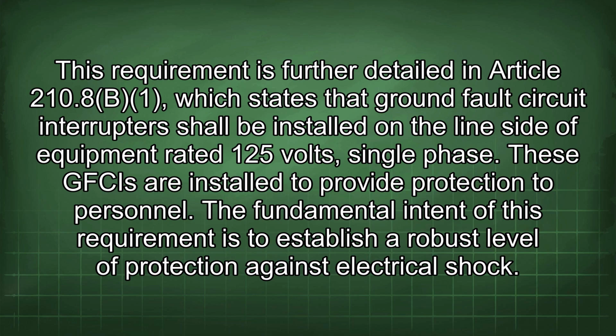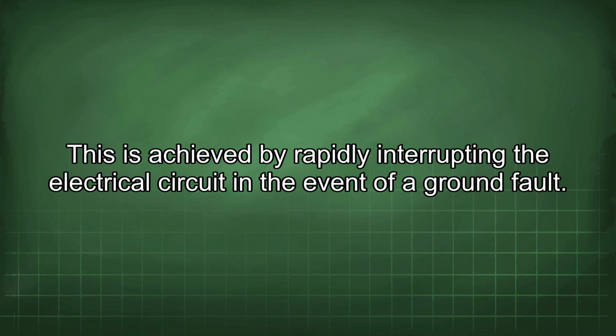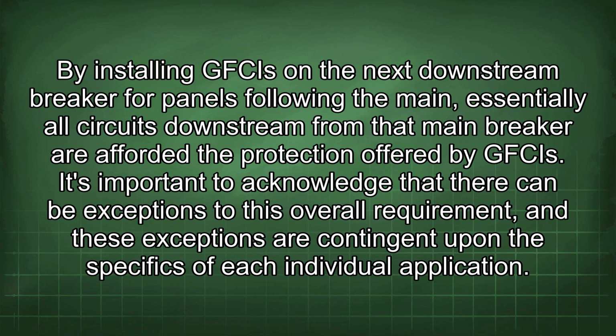These GFCIs are installed to provide protection to personnel. The fundamental intent of this requirement is to establish a robust level of protection against electrical shock. This is achieved by rapidly interrupting the electrical circuit in the event of a ground fault. By installing GFCIs on the next downstream breaker for panels following the main, essentially all circuits downstream from that main breaker are afforded the protection offered by GFCIs.